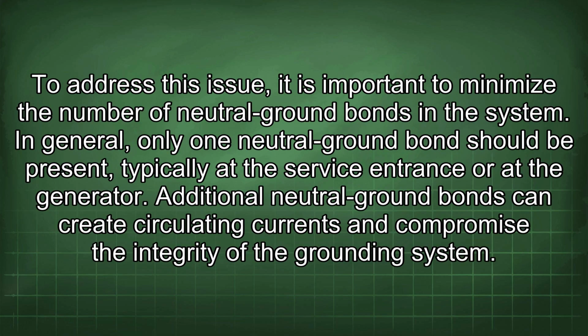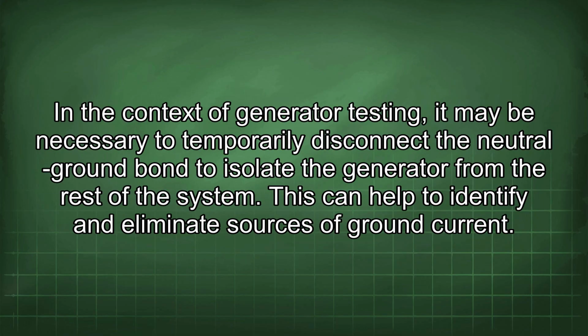To address this issue, it is important to minimize the number of neutral ground bonds in the system. In general, only one neutral ground bond should be present, typically at the service entrance or at the generator. Additional neutral ground bonds can create circulating currents and compromise the integrity of the grounding system. In the context of generator testing, it may be necessary to temporarily disconnect the neutral ground bond to isolate the generator from the rest of the system. This can help to identify and eliminate sources of ground current.